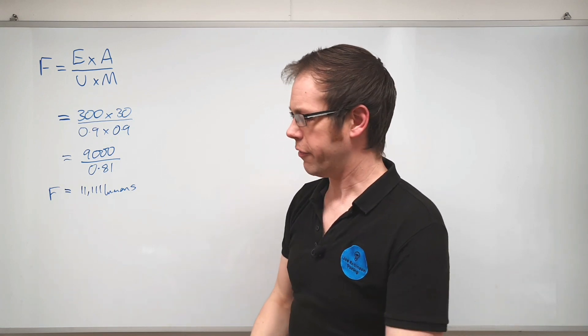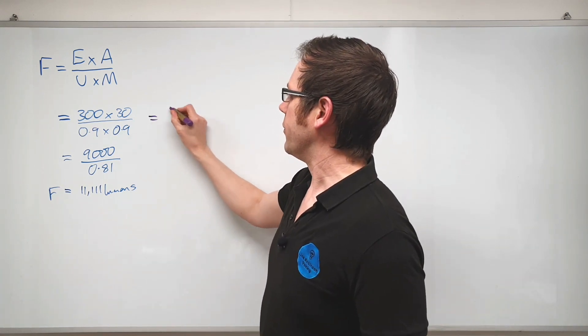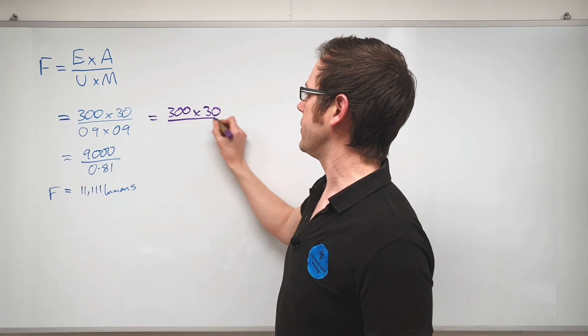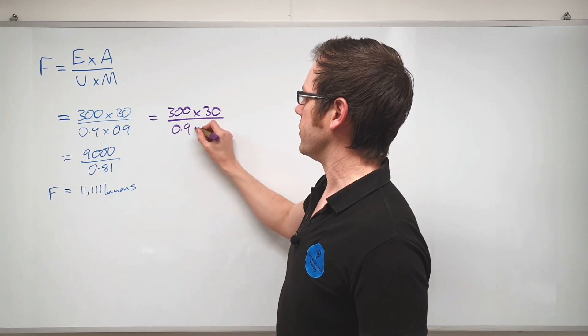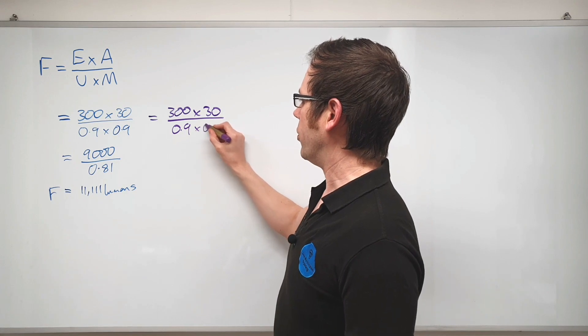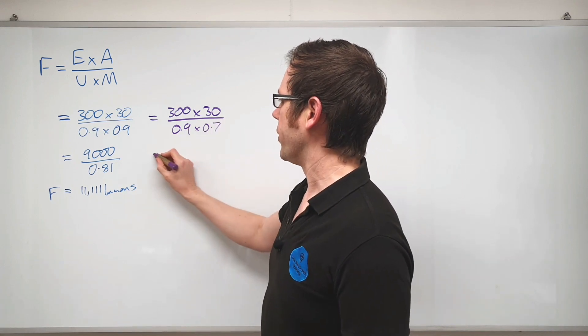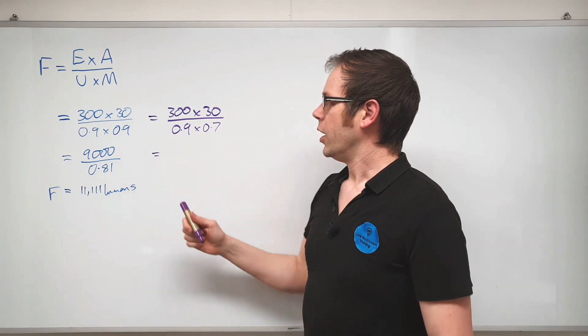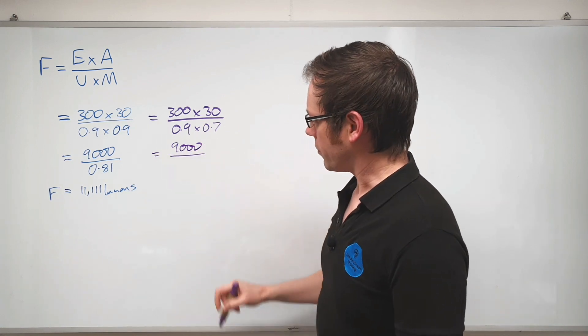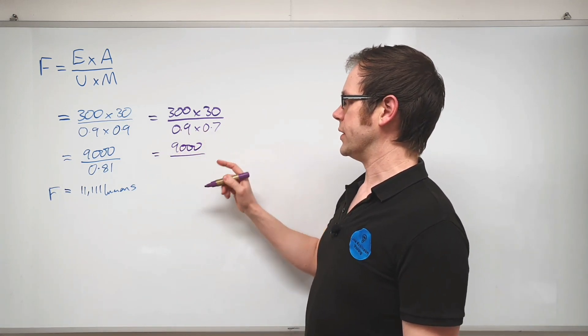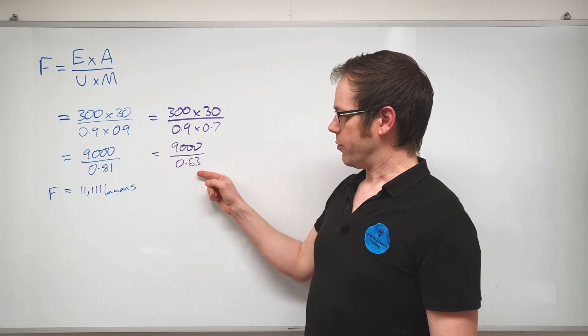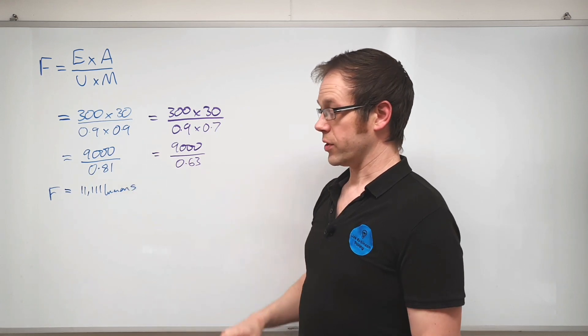So let's say we'll take the calculation from here now. Let's say we're keeping the room the same, 300 lux required times that by 30 square meters, divide that by 0.9 for the utilization, but let's reduce this number now. Let's turn that into something like 0.7 or something like that. What we're going to end up with then? Well again we've got the same number on the top, 9,000—that calculation hasn't changed. And then we've got 0.9 times by 0.7 which is going to give us 0.63.